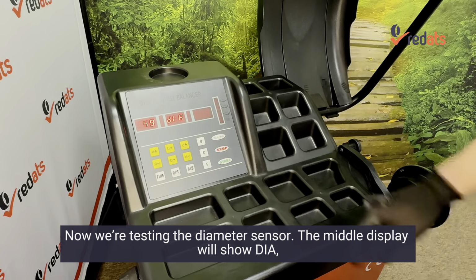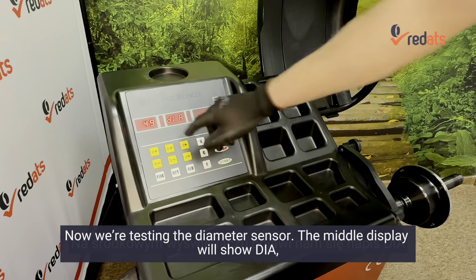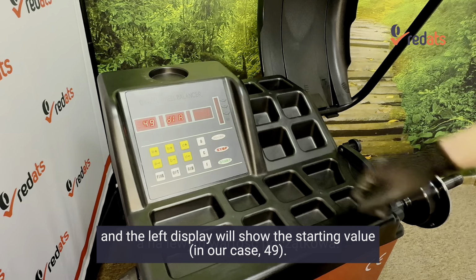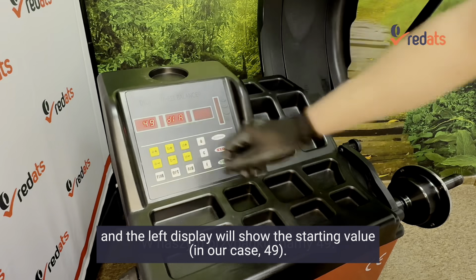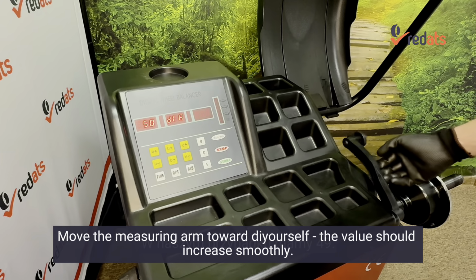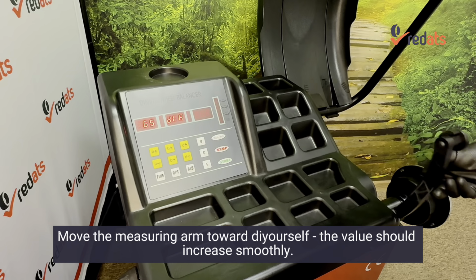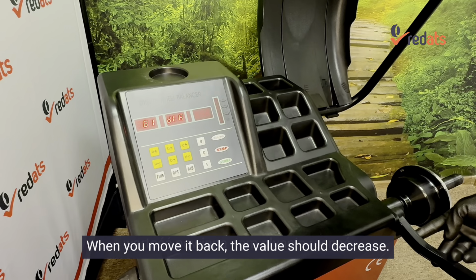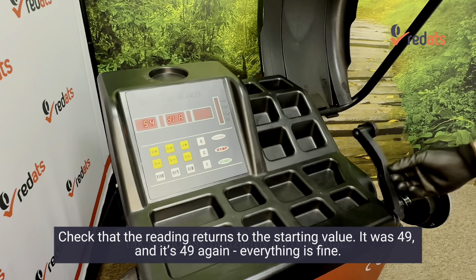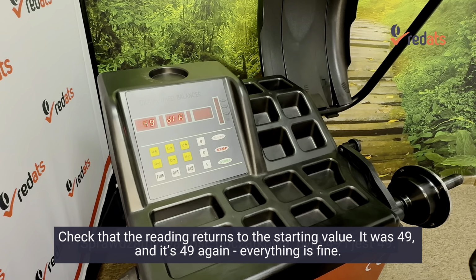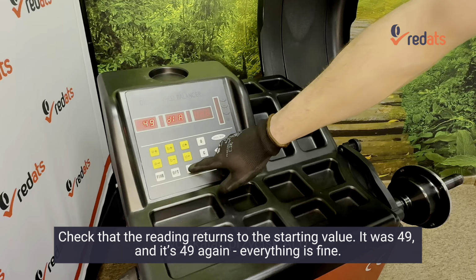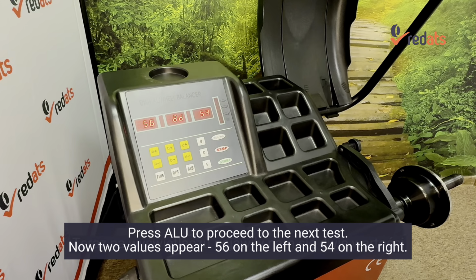Now we're testing the diameter sensor. The middle display will show DIA and the left display will show the starting value, in our case 49. Move the measuring arm toward yourself. The value should increase smoothly. When you move it back, the value should decrease. Check that the reading returns to the starting value. It was 49 and it's 49 again. Everything is fine. Press ALU to proceed to the next test.